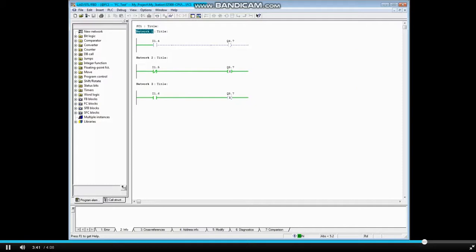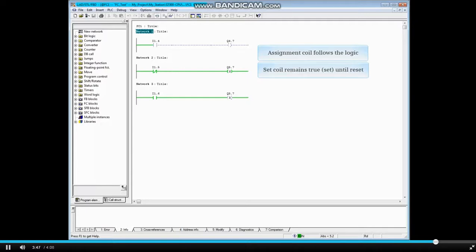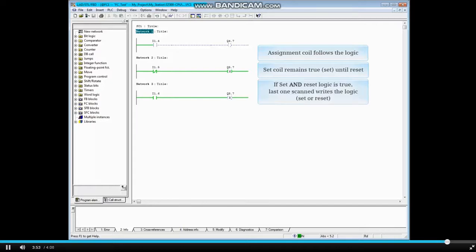In this demonstration you have seen that an assignment coil such as Q 4.7 follows the logic. A set coil remains true until it is reset. If the logic to both the set coil and a reset coil is true, then the last one scanned writes the logic to the output. That concludes this video.